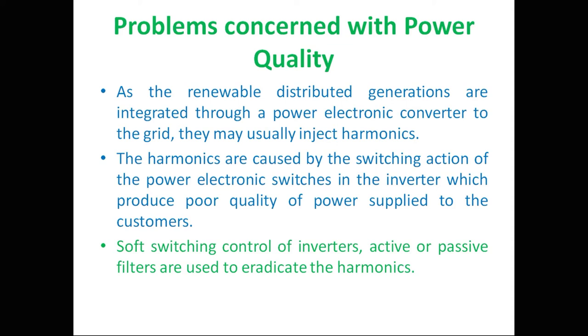Active filters take inputs such as input voltage, input current, output voltage, or output current — sometimes both — and adjust to ensure unity power factor. Passive filters can also be used; they reduce cost compared to active filters for less problematic systems. Sometimes both active and passive filters are used together to achieve very good power quality.